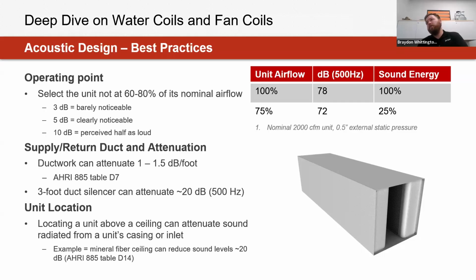And I see a question from Jonathan. Does the selection software calculate noise data at operating conditions? Yes, it does calculate that for both fan and blower coils. And this would be broken out just depending on what airflows and pressures that you're going to be listing for the unit itself. Also a consideration there as well, depending on where this is going to be positioned. So if we're dealing with exposed ceiling or closed ceiling applications, that's when we also could consider or look at different attenuation options for these units, whether it be silencers or attenuators to try to minimize the amount of breakout noise that's going to be coming from that unit or from that fan.